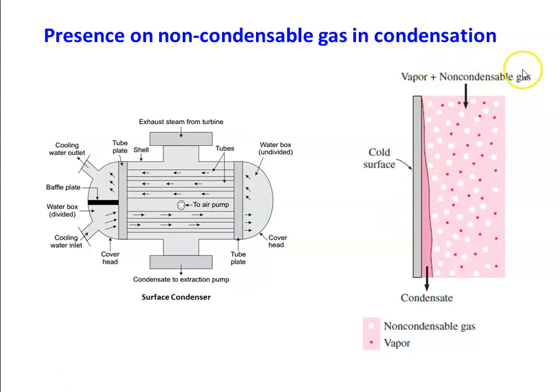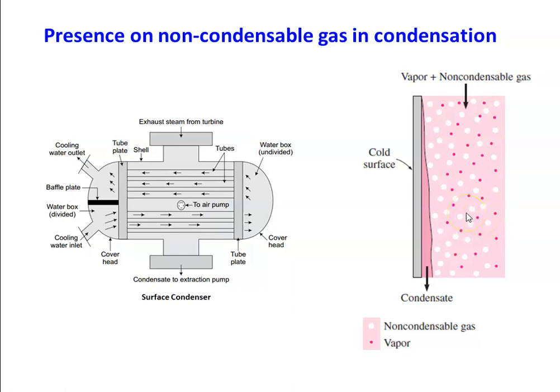Air is one non-condensable gas. When non-condensable gas is present inside the condenser, there is a blanket of this gas near the surface. The incoming vapor must penetrate through the non-condensable gas to reach the cold surface for condensation. This restricts heat transfer, so effective condensation may not take place. As a result, the amount of condensate, heat transfer, and heat transfer coefficient all decrease.